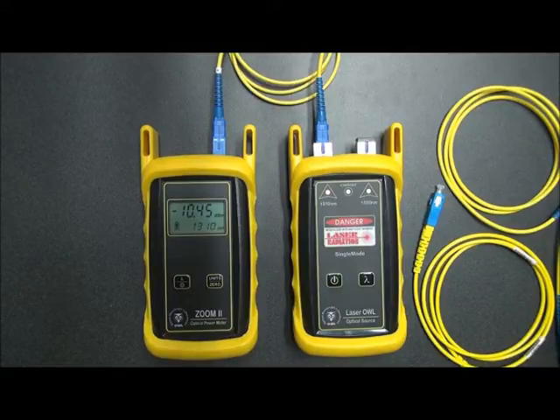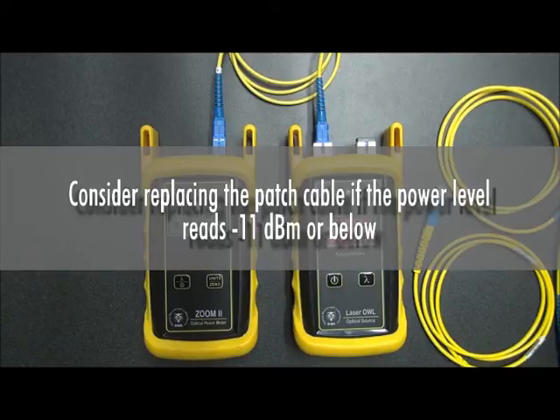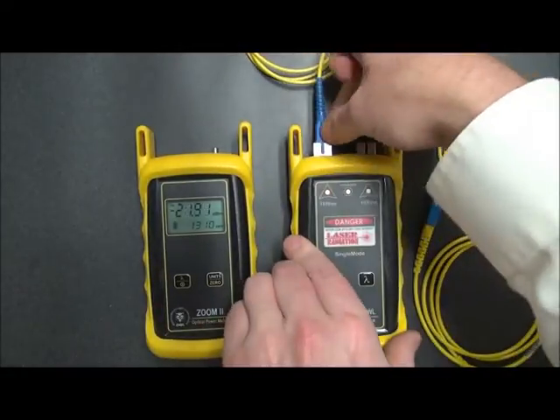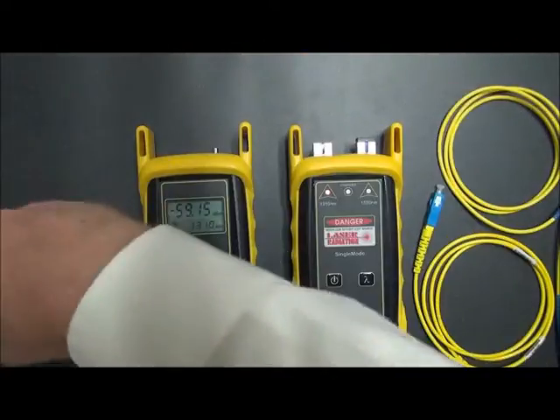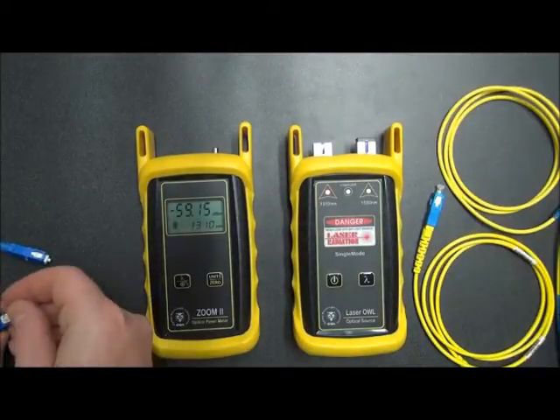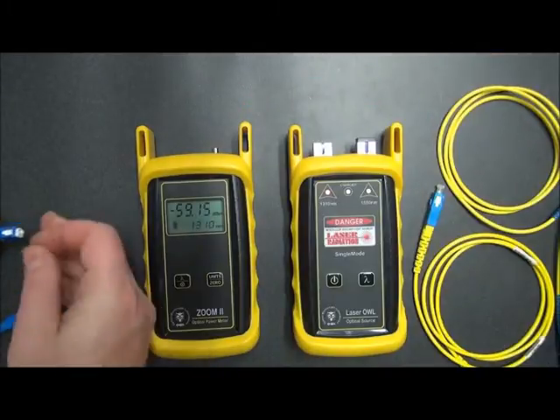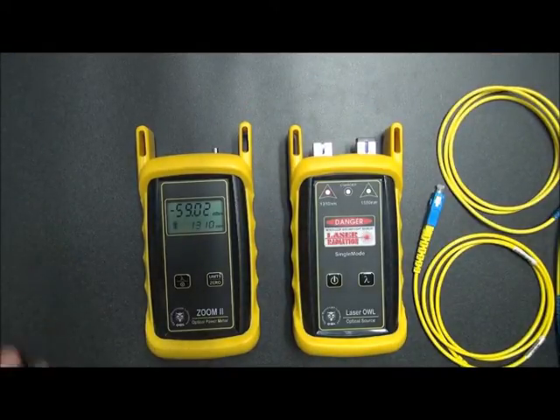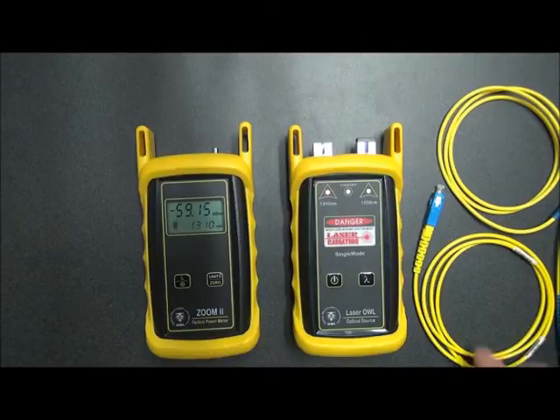What we're concerned with is that the reading does not exceed minus 11 dBm. Once it does, we want to consider replacing the patch cable. Since we've determined this cable is good, we simply disconnect it from both testers and set it aside. We will not need this cable again until we start performing our insertion loss measurement.